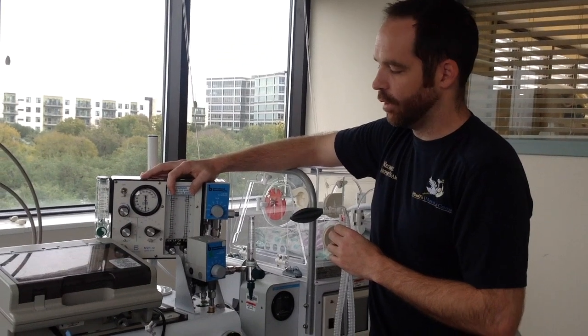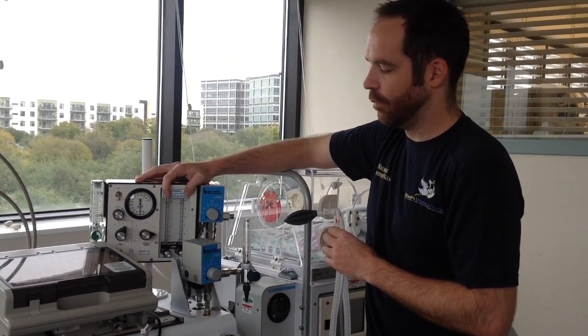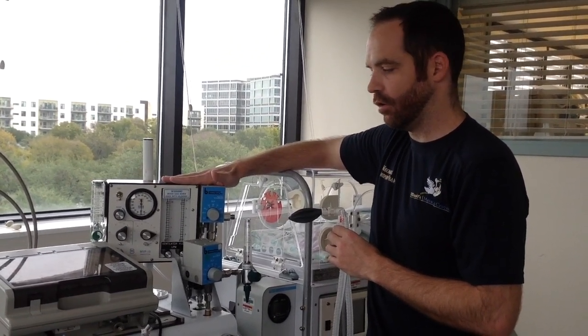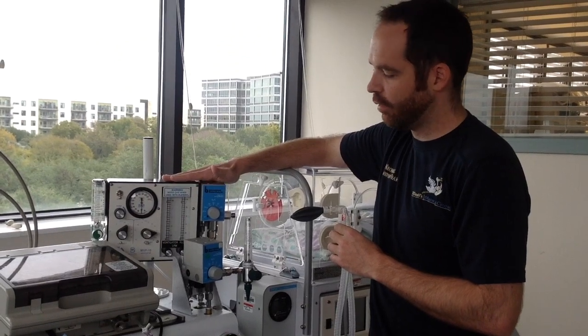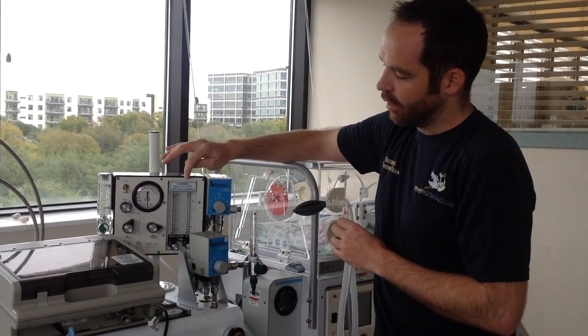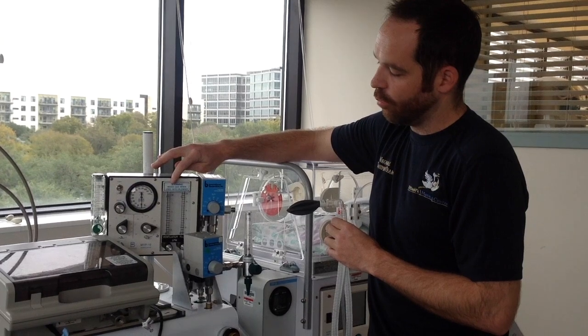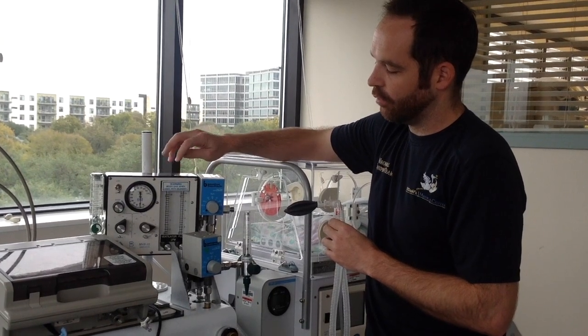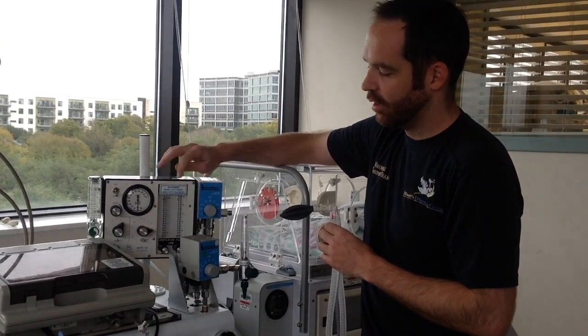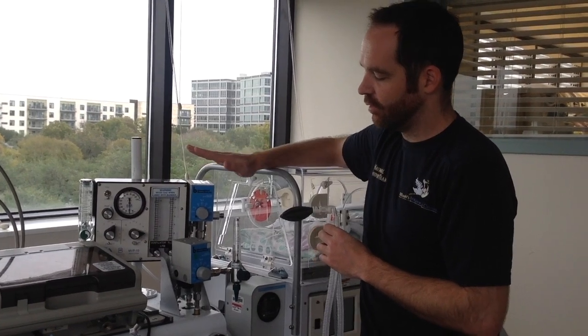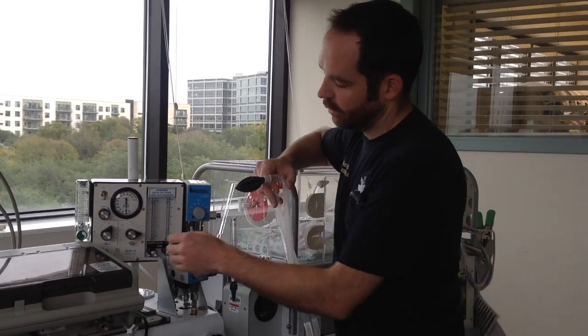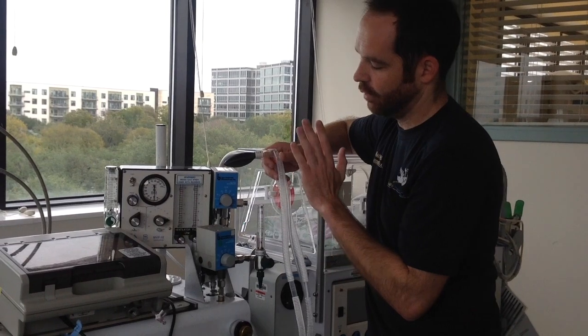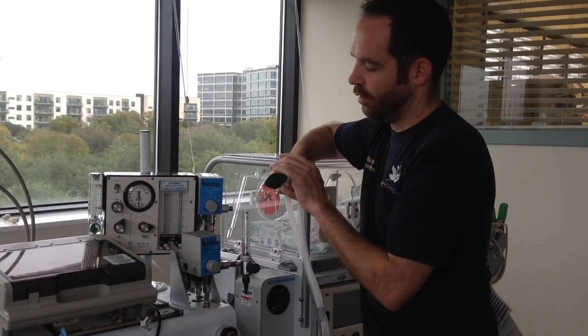You see the 2 flow meters. That exists from a time where blenders weren't as used as much as they are now. So you might find some of them saying warning mixed gas, or some might say air oxygen. But just remember, when you have it set up through a blender, all you need is just one flow meter to start putting some flow into the circuit.